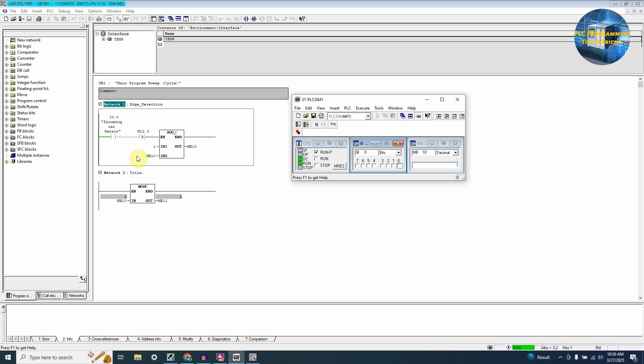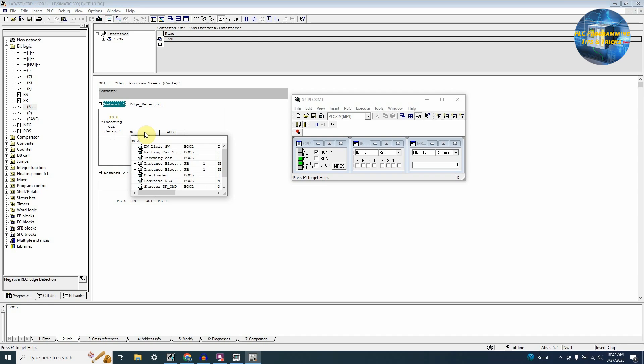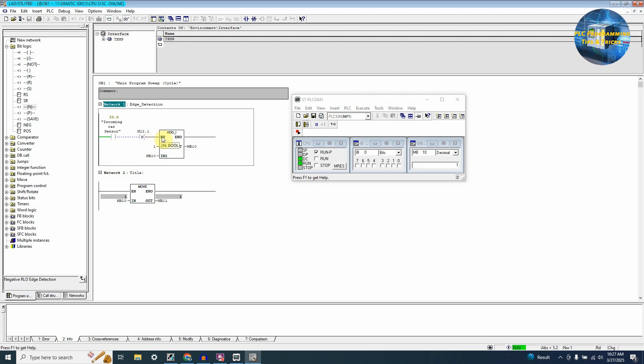Now let's see how to detect the falling edge of this sensor. We go to bit logic and insert the RLO negative edge detection, delete the positive instruction, and assign it M12.1, then download to the PLC. This instruction will not send a pulse to the add function while the sensor detects the car, but as the car leaves in front of sensor I0.0 and the sensor is no longer detecting it, in that scan cycle the instruction sends a pulse — the falling edge trigger — to the add function.